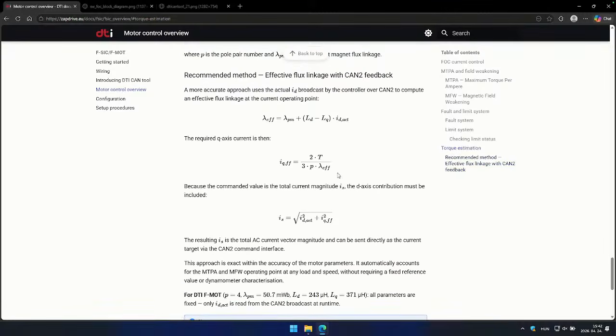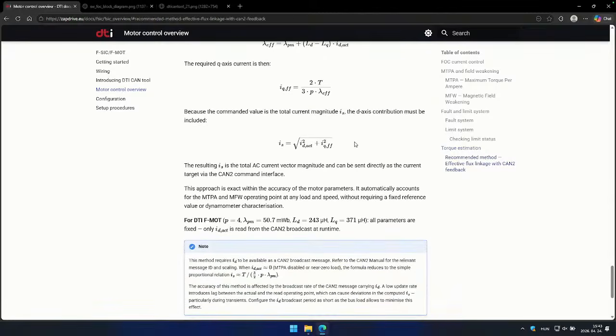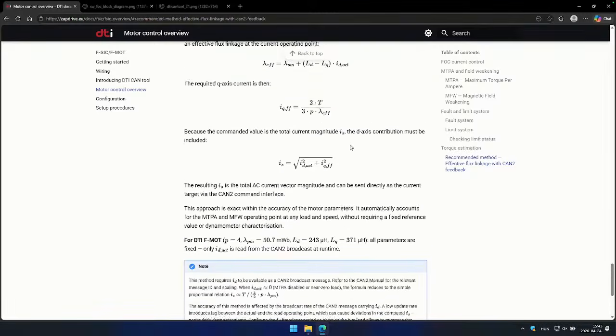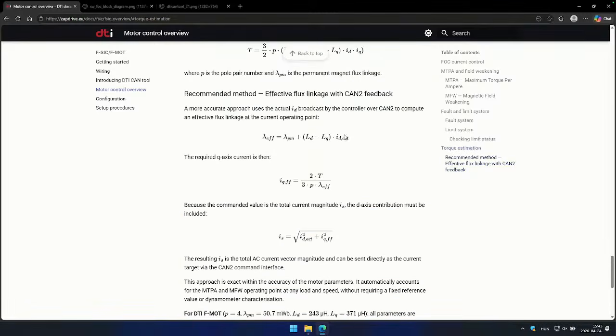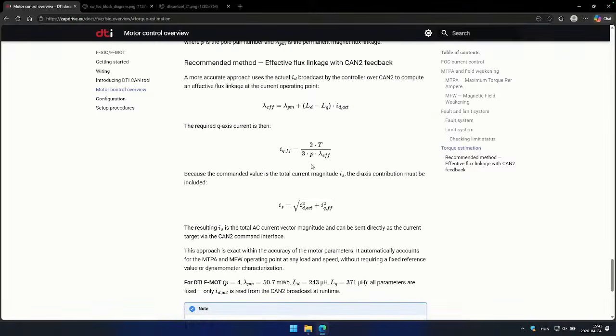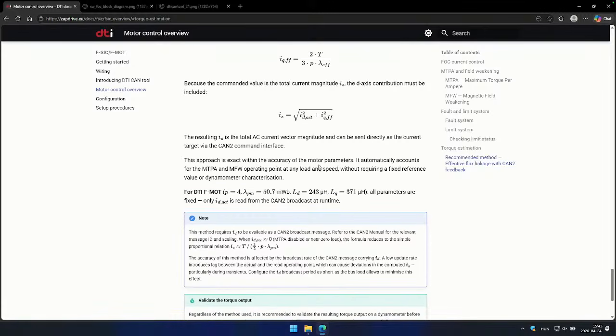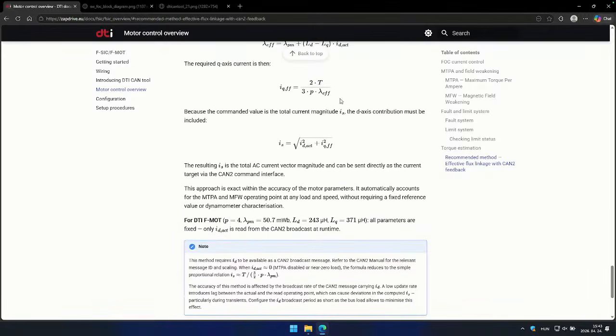If you're using this in a fast loop, where T is the torque, you're able to send a current command which includes your torque demand, and it can provide you the desired torque. This is feed forward, so you use the CAN2 feed for the ID actual current, but the rest can be calculated and sent back to the inverter. So you do not need a PI current controller for this method.